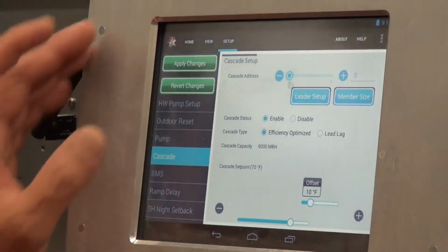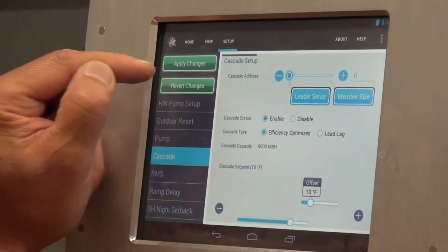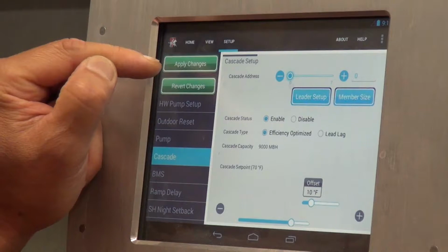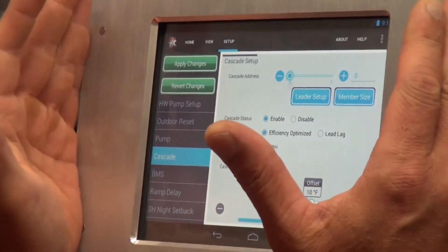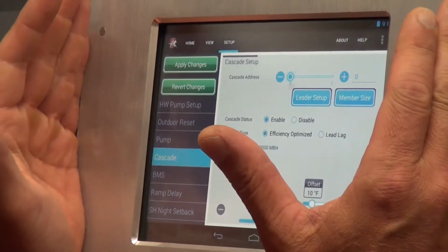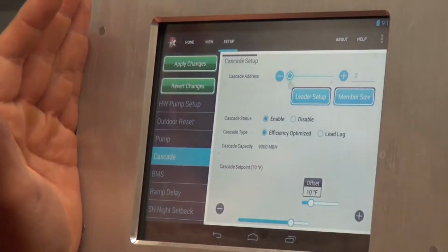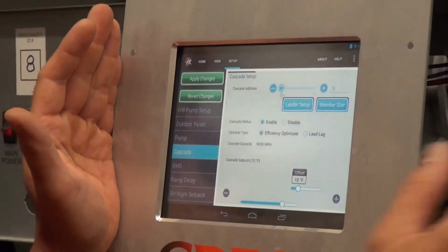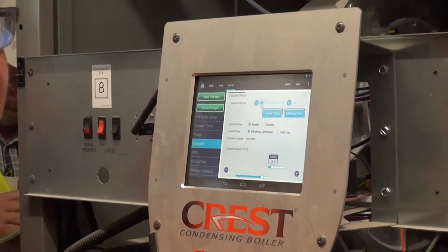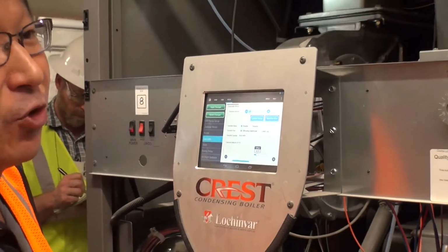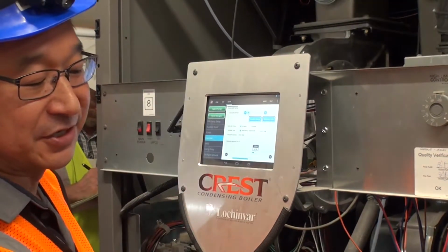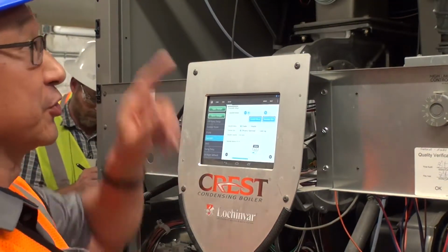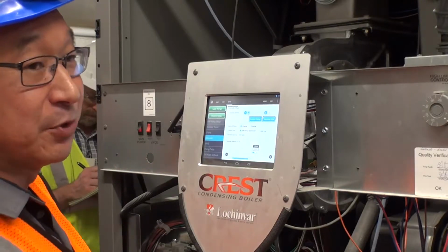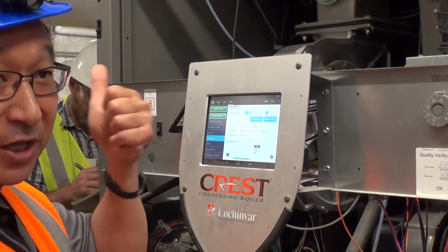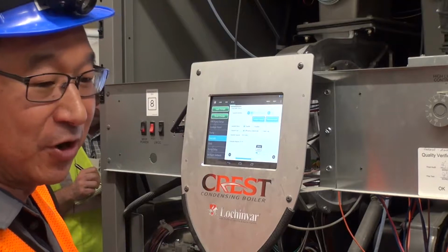So we have to go over to that one and apply the changes. Once you make the change, what I told this boiler is don't pay attention to the energy management anymore. Then we're going to go to this boiler and tell it it's number 1 now. With this boiler off, now it'll control, but the bad thing is it'll only control off of its outlet temp sensor, not the system sensor. That's the beauty of adding the special dual element sensor to do the alternate leader.